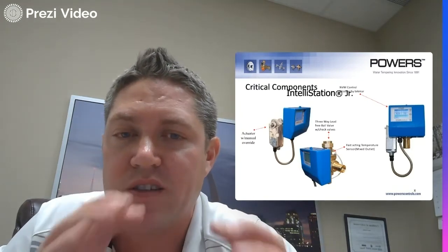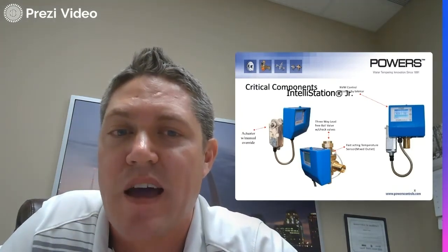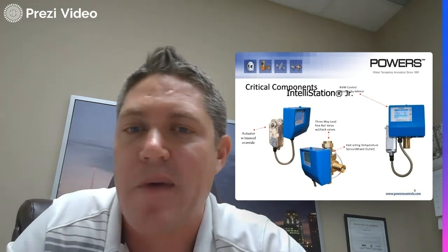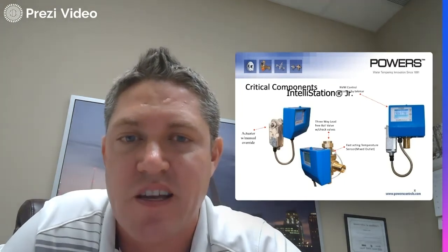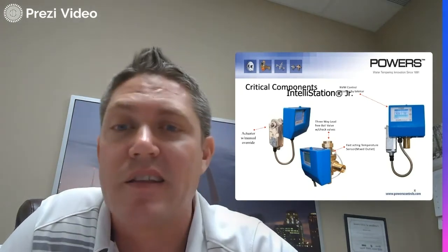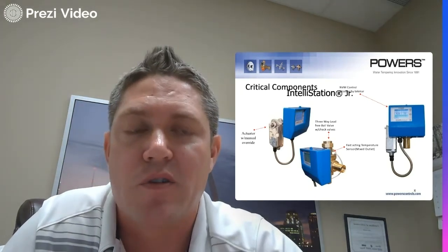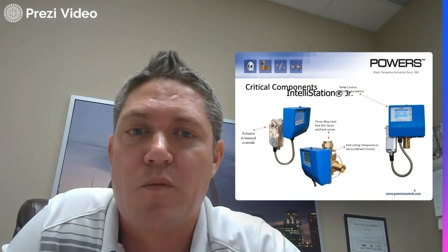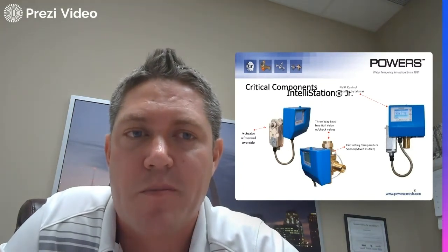The controller is bolted right there to the actual 3-port balancing valve, with the same actuator as the original Intellistation has. And these are a lot less expensive than the full Intellistation Sr. that was first brought out onto the market by Powers.